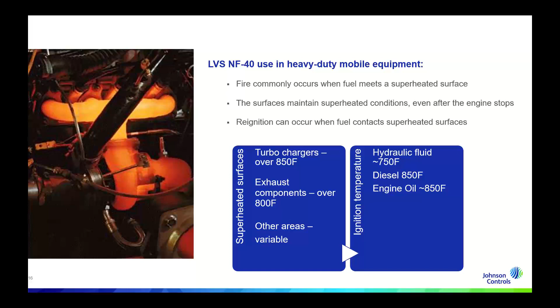In 2011, the ANSUL LVS system was released as a standalone suppression system, providing both cooling and suppression capabilities. Even with the FM approval of the system, like I mentioned, there's still standards that require the use of or recommend the use of twin agent suppression systems for equipment, such as we would see in NFPA 120 or 122. In support of the liquid-only position, as we expanded our liquid suppression product line, we introduced the NF40 LVS and produced a white paper based off of the testing and documentation that we have to support that liquid only is equal or better in performance than what we have seen with our twin agent.